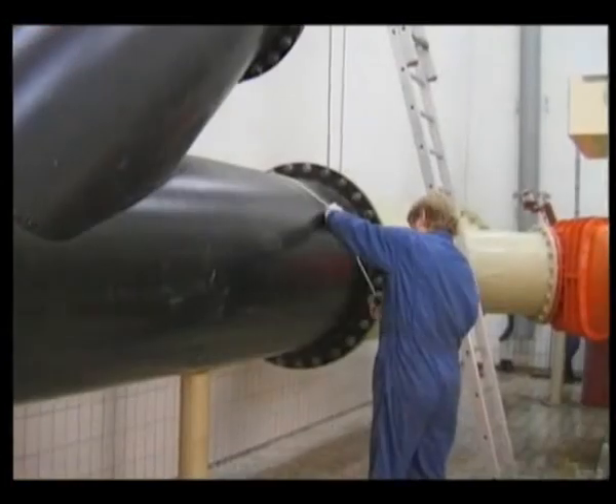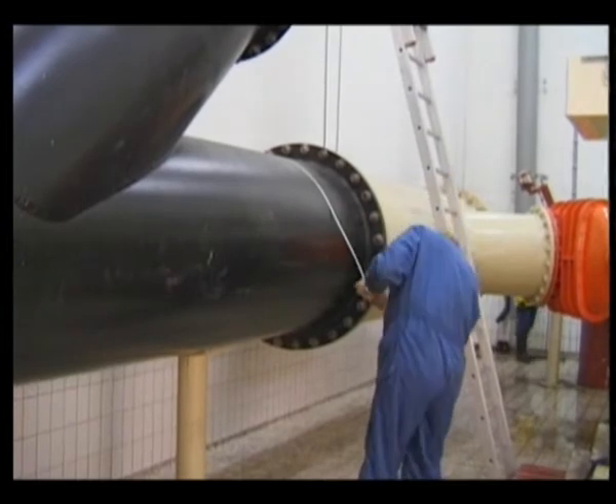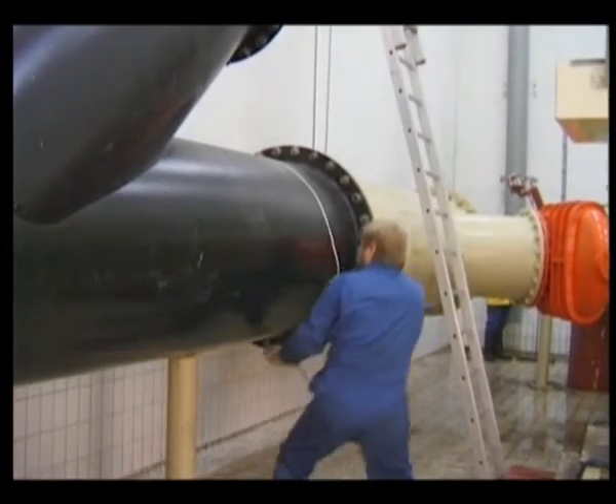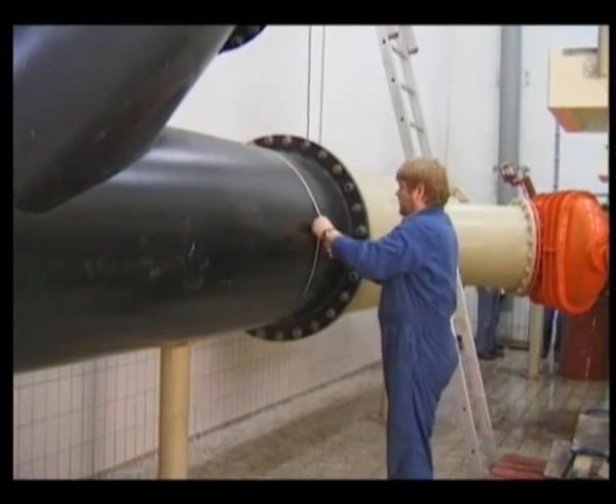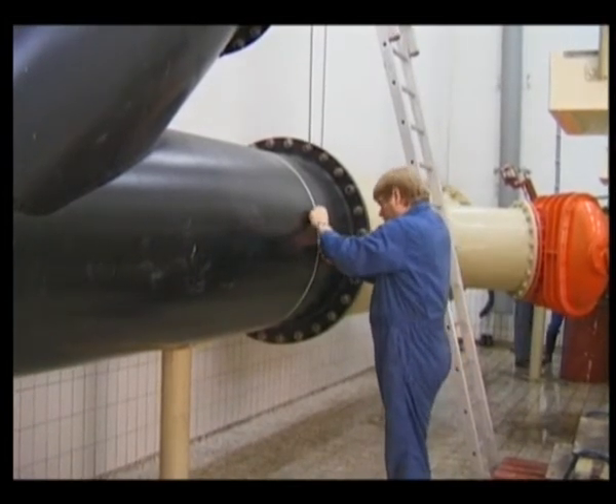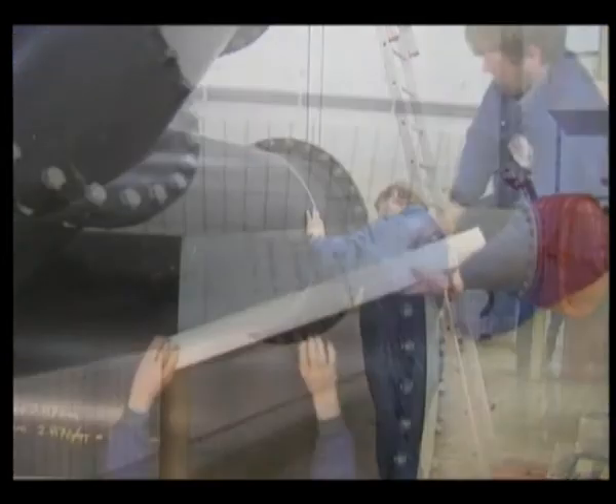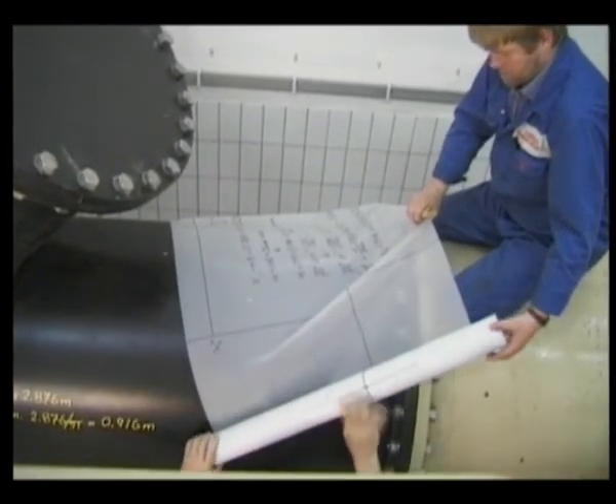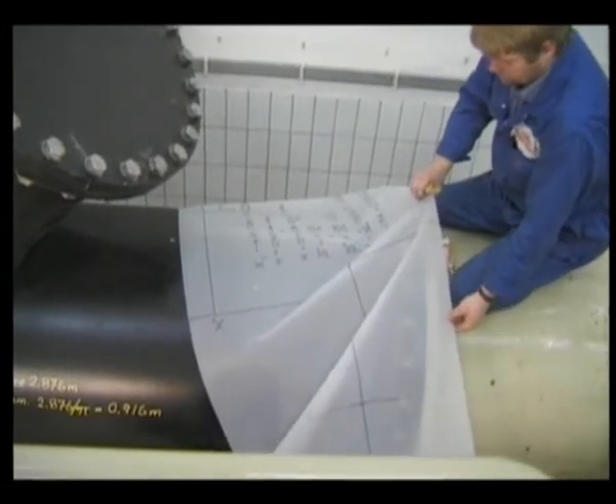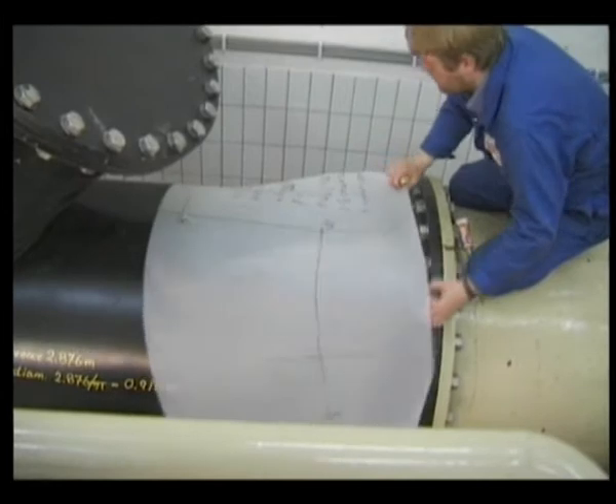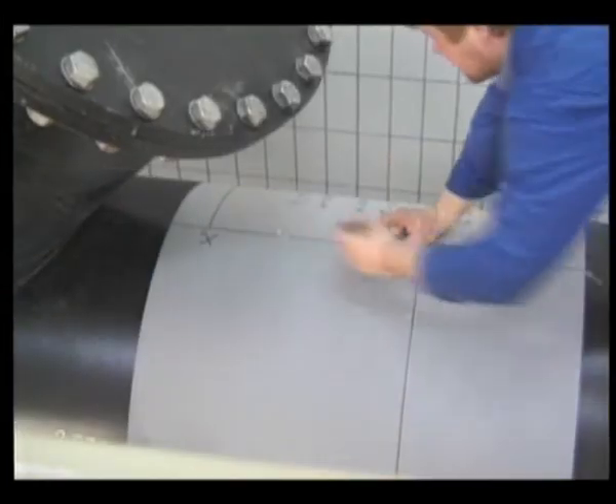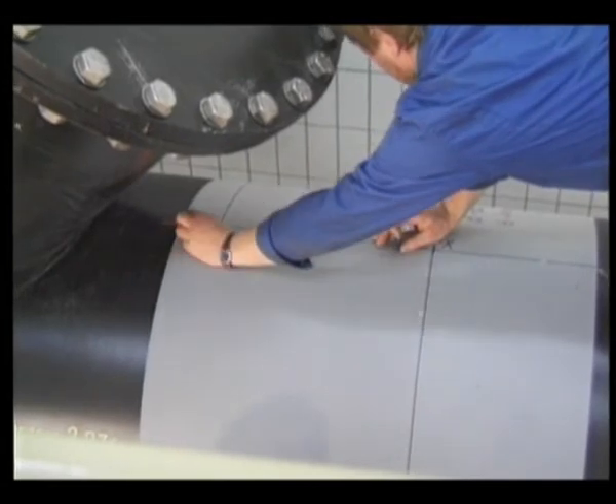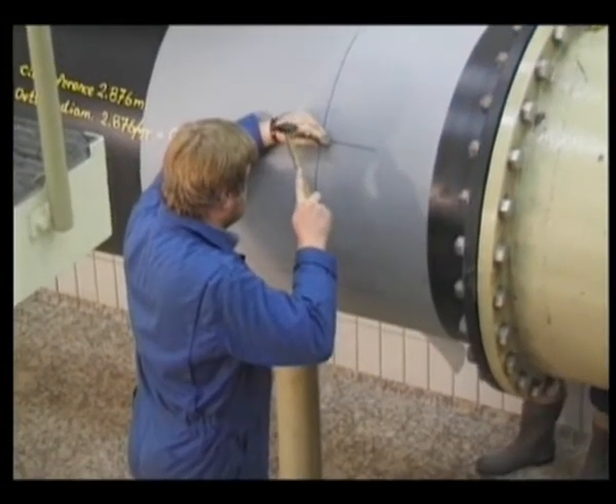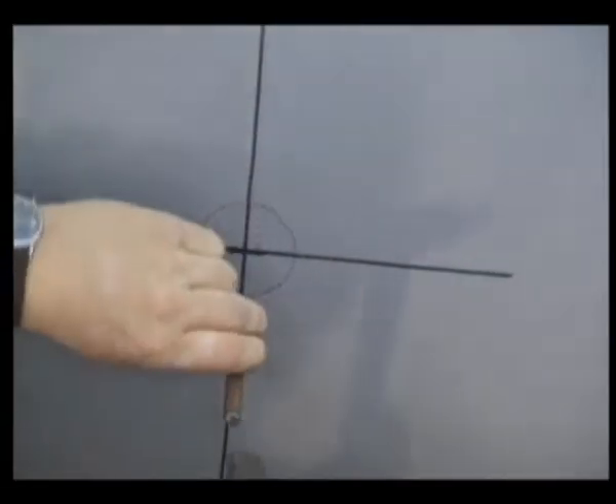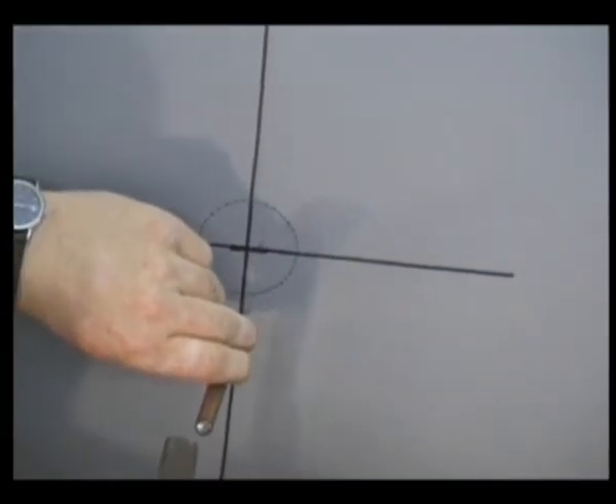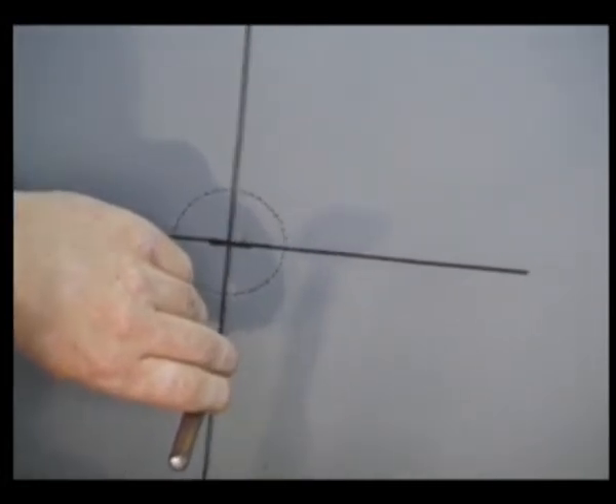We're now at a real two-track Sonokit installation at a wastewater treatment plant in the Netherlands. Having measured the circumference and having made the drawing, we can place the drawing as we saw earlier in the film. Here we see how the points P1 and P2 are marked with a centre punch. Make sure that the lines are marked outside the circle so the cross lines can be recreated after the holes have been made.